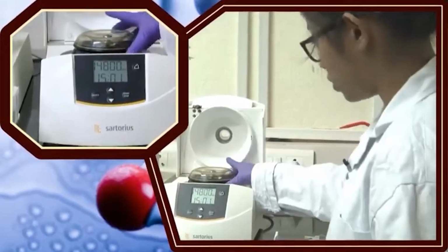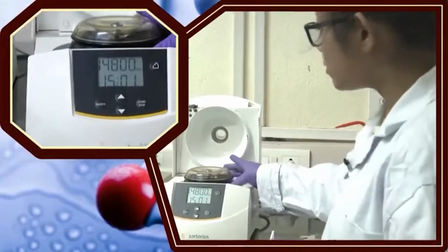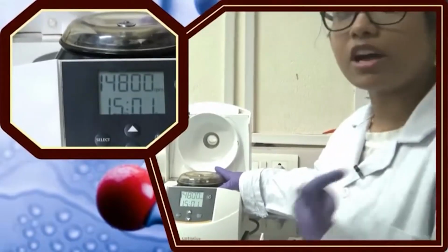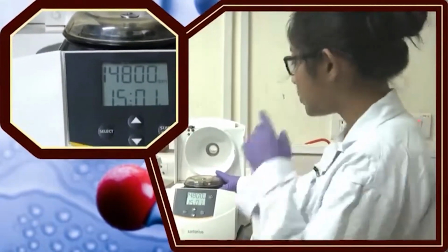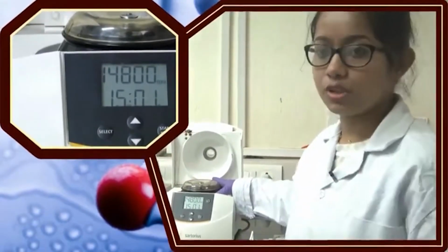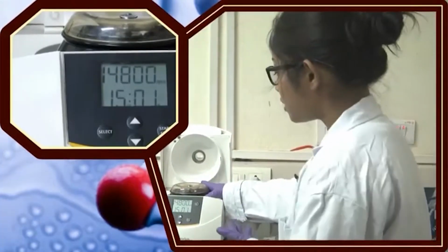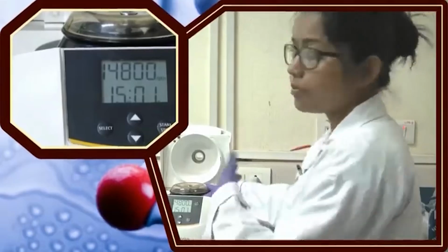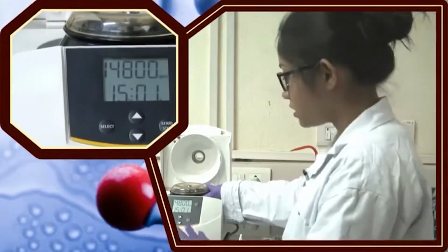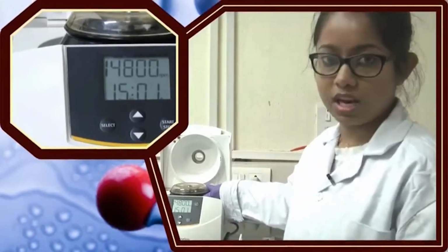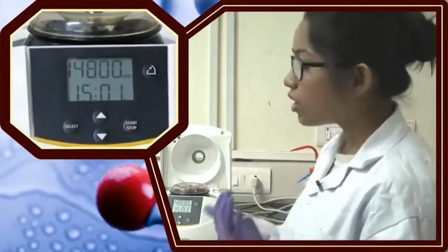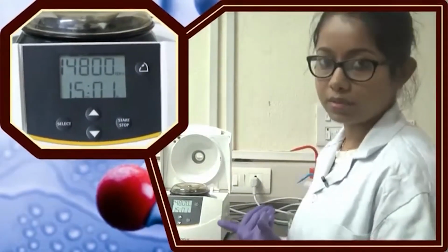This is called the rotor of a centrifuge. Suppose it is rotating at 5000 RPM, that means per minute it is rotating 5000 times. It does not depend on the size or the radius of the rotor.